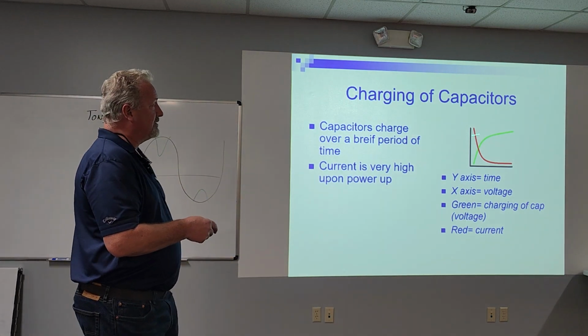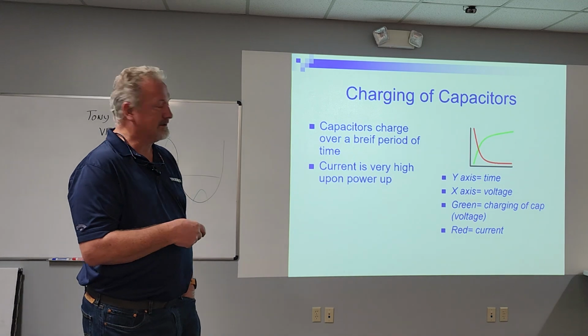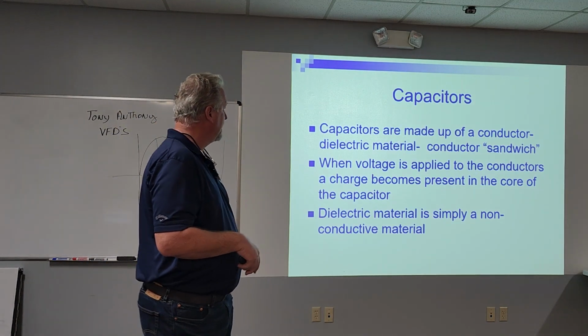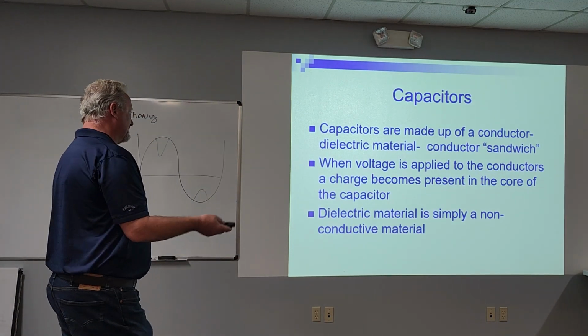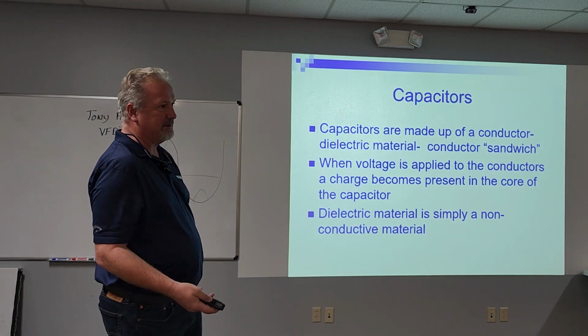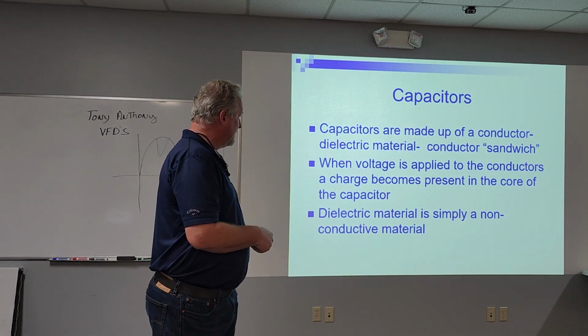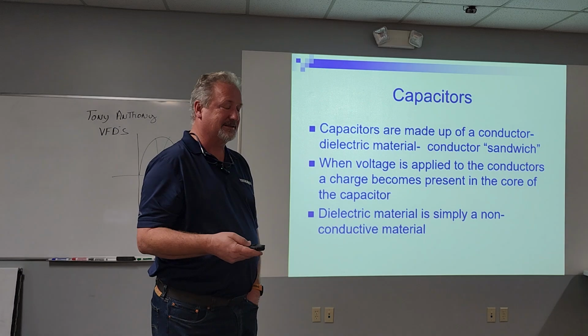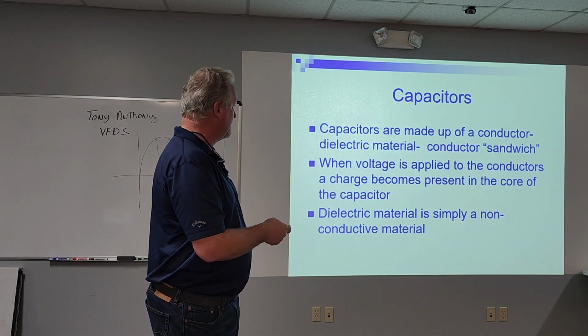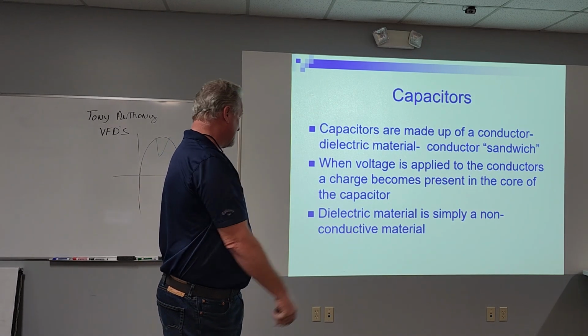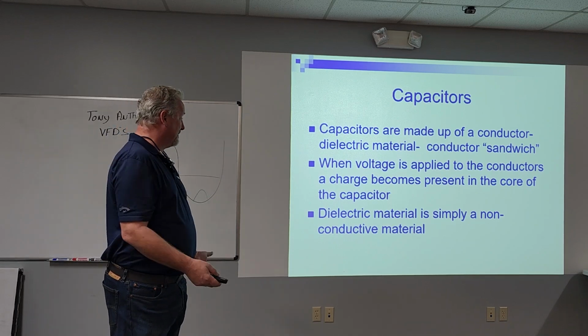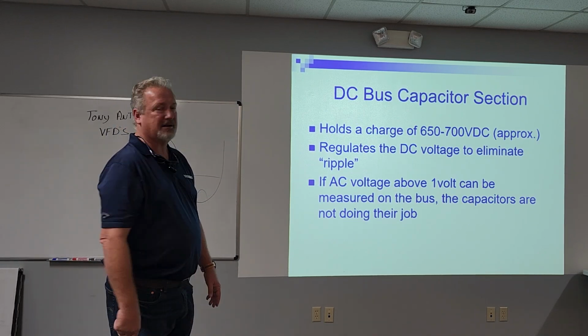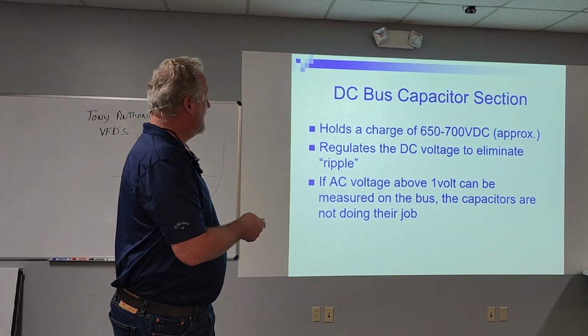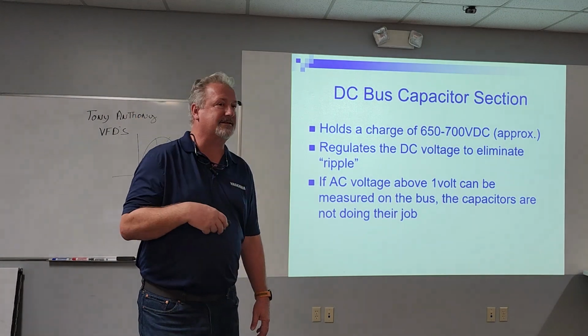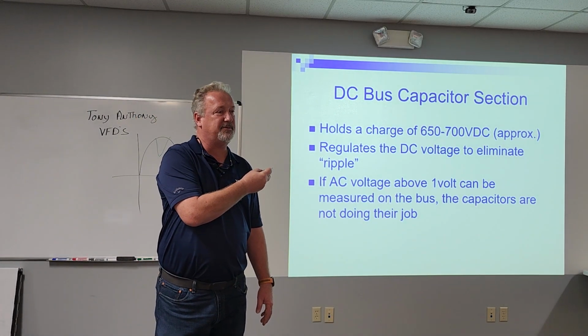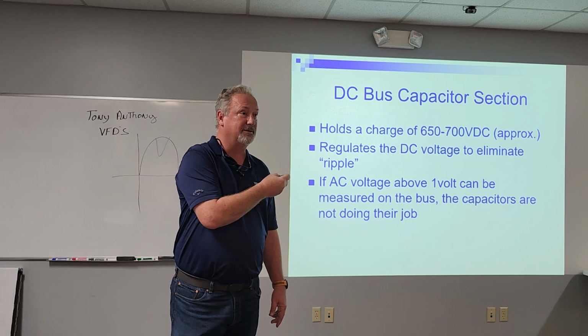But this is why we talked about that pre-charge relay and having that resistor in there. This is just showing it. Capacitors are made up of a conductor-dielectric material-conductor sandwich. When voltage is applied to the conductors, the charge becomes present in the core of the capacitor. The dielectric material is simply a non-conductive material. Basically, the capacitor charges up and holds a charge of 650 to 700, and that's how much times your input voltage? 1.44.